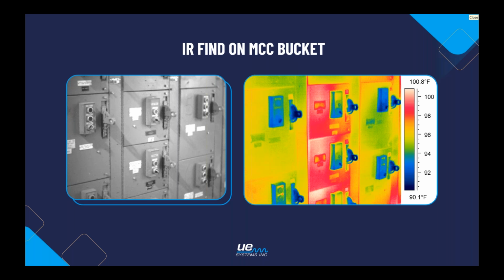Looking at that image on the right, that bucket is something I do not want to be standing anywhere close to. So that gives me the immediate caution of I don't want to close the distance to do an acoustic inspection of this while it's energized, because clearly there's a severe issue going on. So using both at the same time makes us a very, very safe inspection.